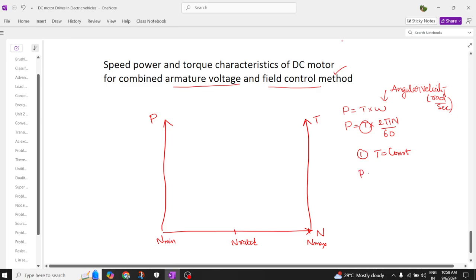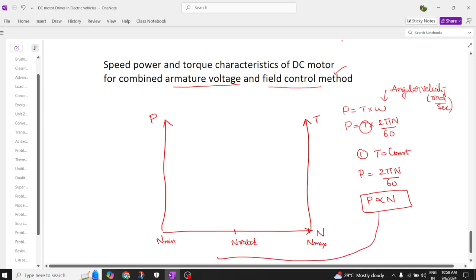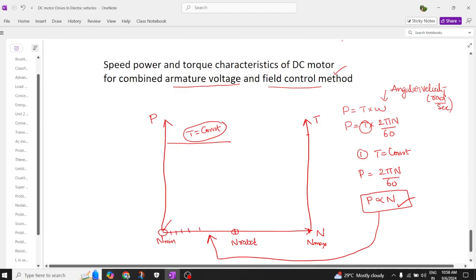The first condition assumes torque is constant. When torque is constant, power equals 2πn divided by 60, so power is directly proportional to speed. From minimum speed to rated speed, the torque magnitude is constant. As speed increases from n-minimum to n-rated, power also increases proportionally — power is directly proportional to speed.